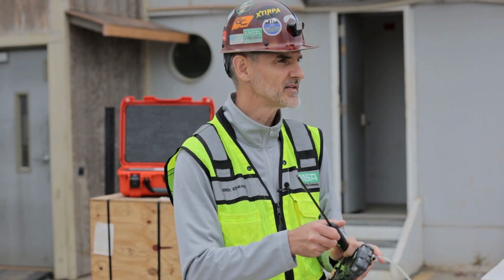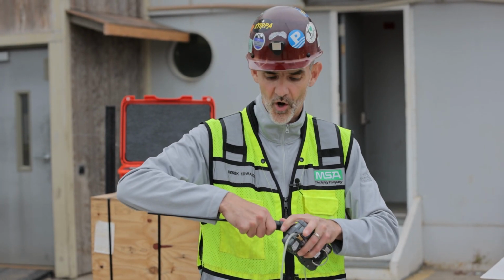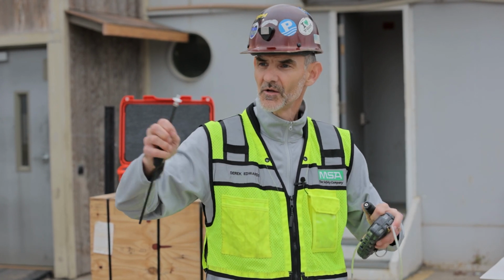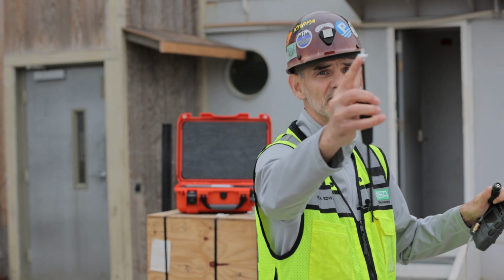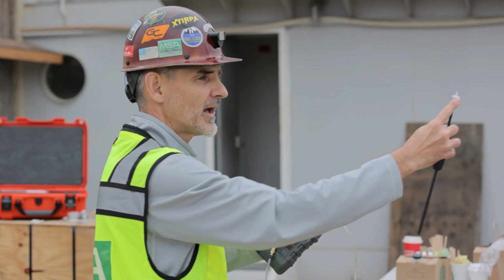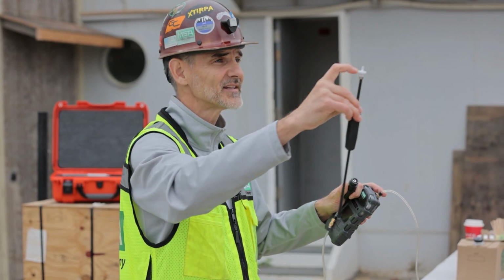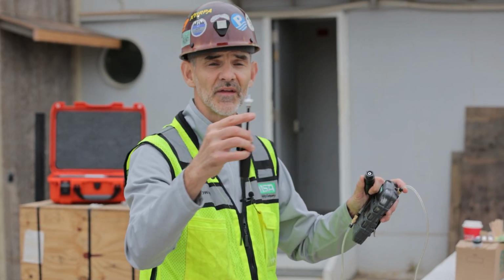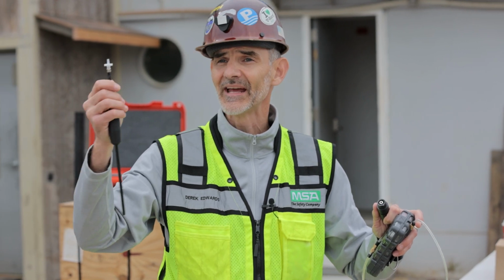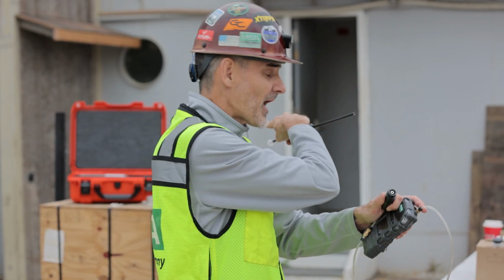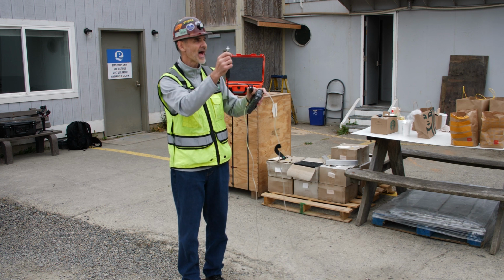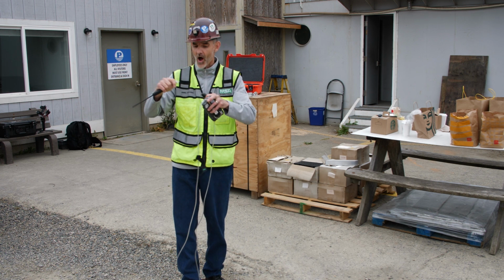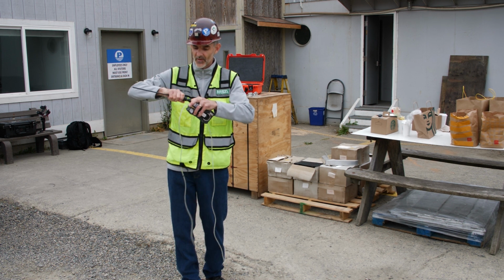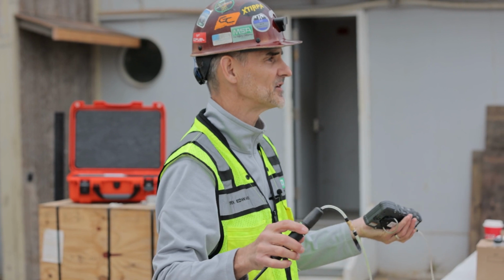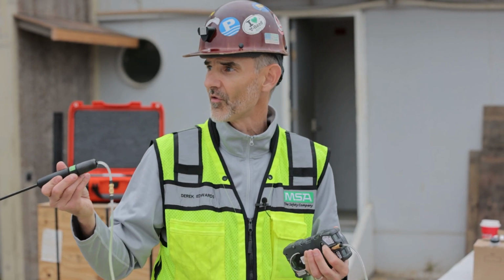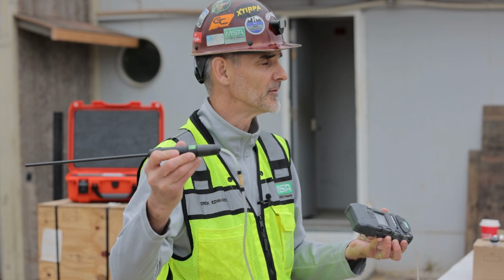We try to keep water out of these instruments for sure, and definitely out of the end of the probe. Inside this probe, probably can't see it, is a very small replaceable water and dust filter, okay? If you put this into water, that is going to stop the water from going through the hose and into the instrument. If you fill this up with water, it needs to be replaced, okay? Hopefully you have some extras in your case. I'll talk to Matt about that. But you're going to want to replace that, because if it gets full of water and then you clear that pump, it's going to go right back into pump alarm because it can't pull a sample through all of the water that's in that filter. So that may be the problem.